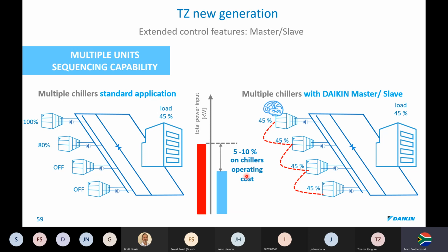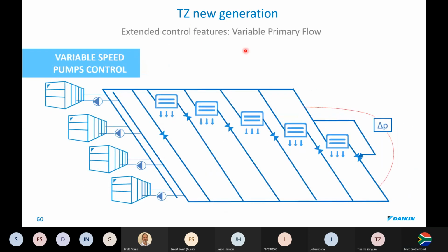And here you can see by this configuration, you can save up to 10% operating cost. And considering what these chillers consume in kilowatts per hour, it's phenomenal saving over the year. 10% is phenomenal. We also offer, as I mentioned earlier on, the variable speed control on the chilled water pumps for variable primary flow. The important thing is on your furthest load, you have to have a pressure differential switch, which tells these pumps how fast to spin and how fast you run the motor to pump. And important, you need this bypass line for surplus and deficit flow.